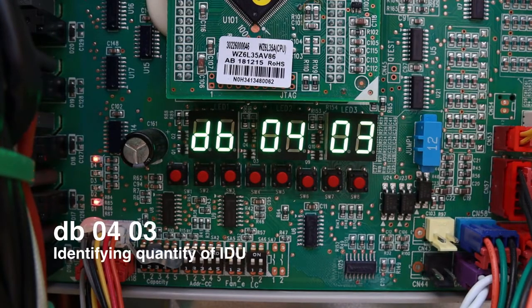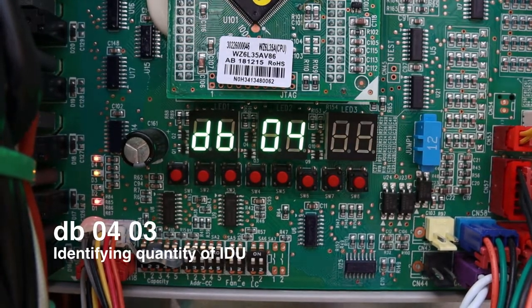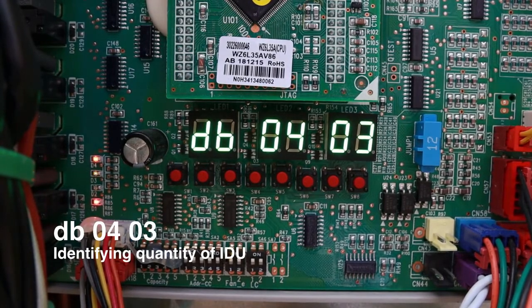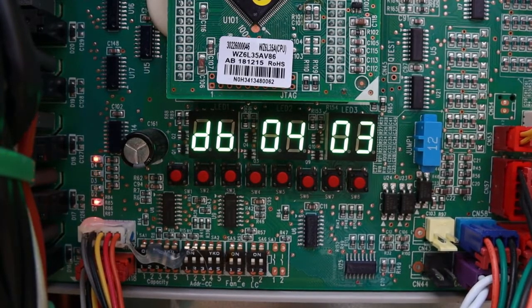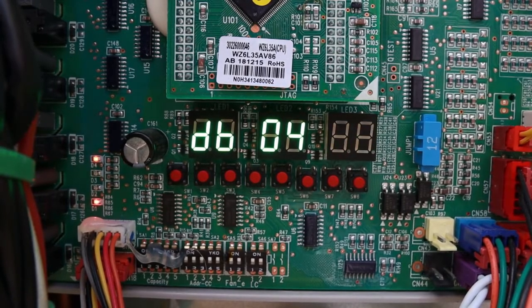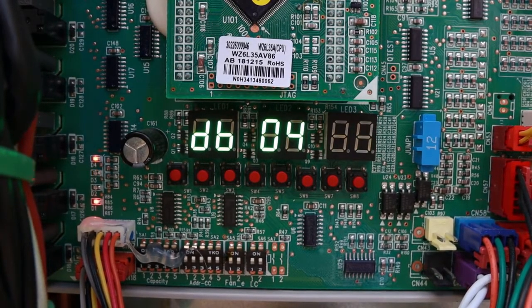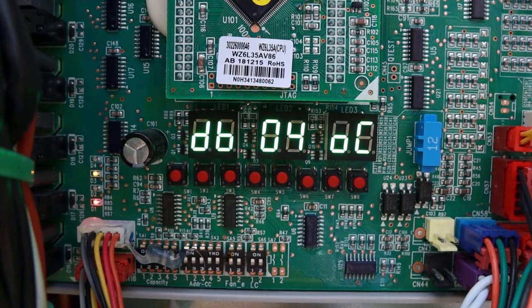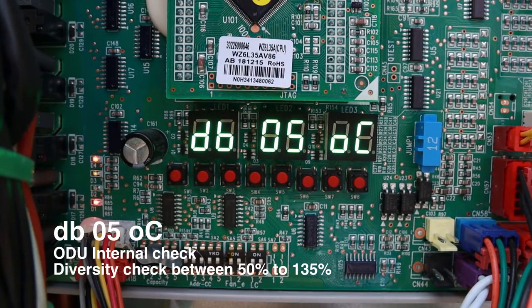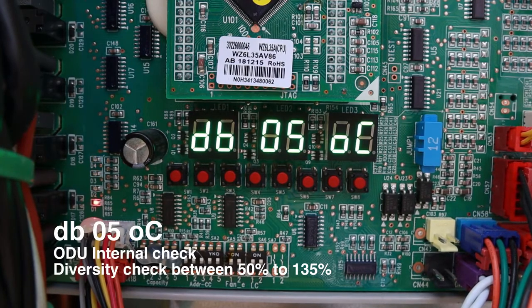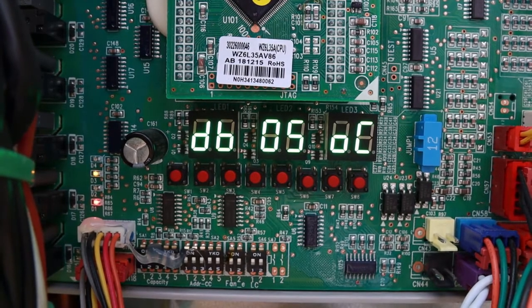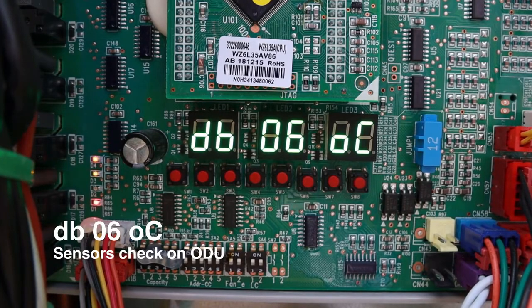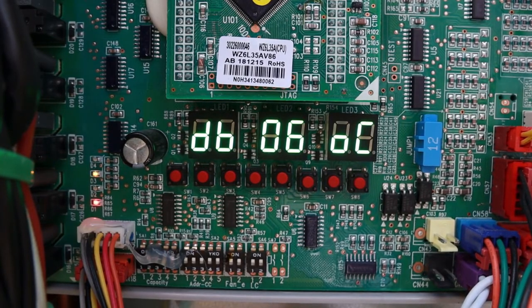Step 4 asks to confirm the quantity of evaporators. As I showed before, I have 3 units in my house, so 3 is correct. I press SW7 to confirm the quantity of evaporators and wait a second until it accepts the command — about 2 seconds to move to step 5. Step 5 performs an internal check on the condensing unit, especially the diversity of the system, so just give it a second. Step 6 does a sensor check for the condensing unit, which is also automatic.